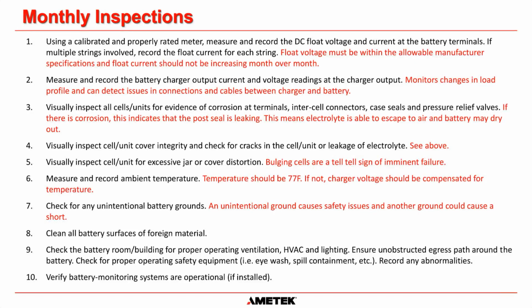And also, let's say there is a negative ground on the battery. It's not going to affect the operation of the system. But if a positive ground comes along after you have a negative ground, then you have a direct short, and that will cause huge issues. That's why we check for unintentional grounds.